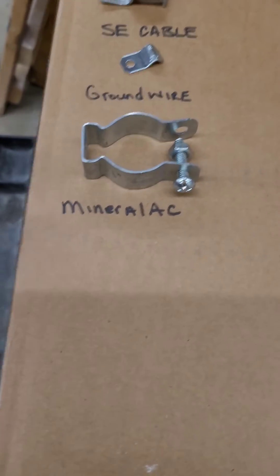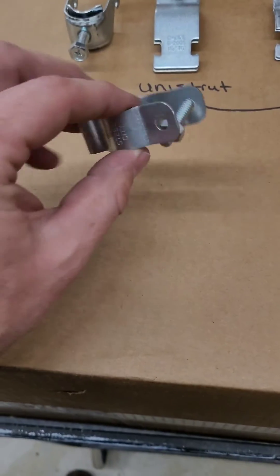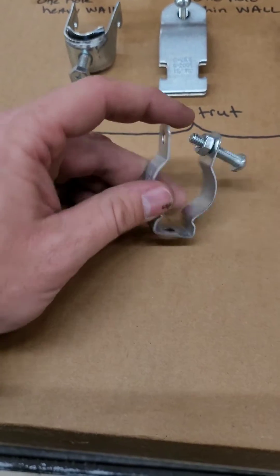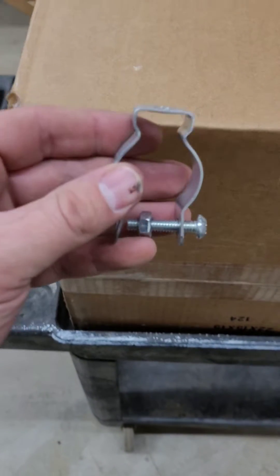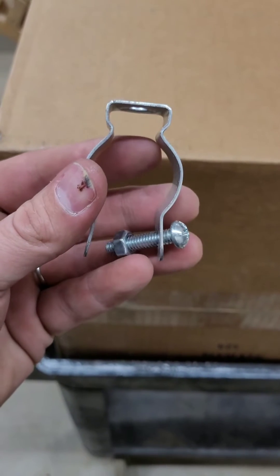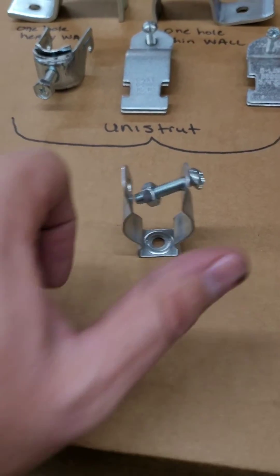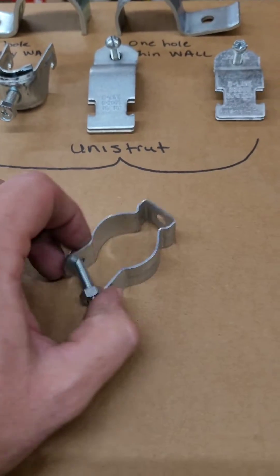And then we have what I call a Minerallac strap. You would take it and screw it. Most of the time you've got to take this bolt out and either drill your hole for concrete or just go ahead and put the screw right through the back and it mounts right to the side. If you're doing conduit bends you need to account for this little offset because your conduit will only come to about where my finger is. Then you just lay your conduit in it and squeeze it around, run the bolt through. Sometimes you have to use a channel lock to get it to pull around if you're going over an uneven surface or something like that.